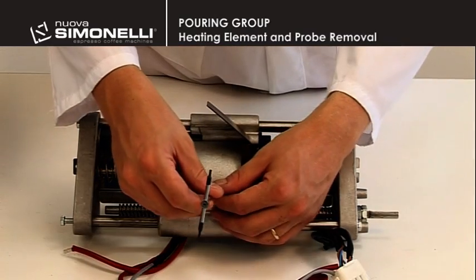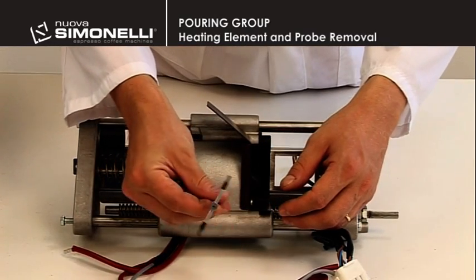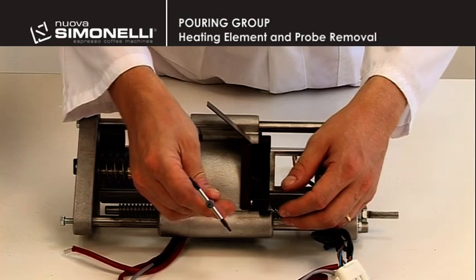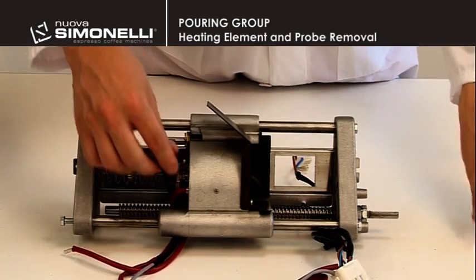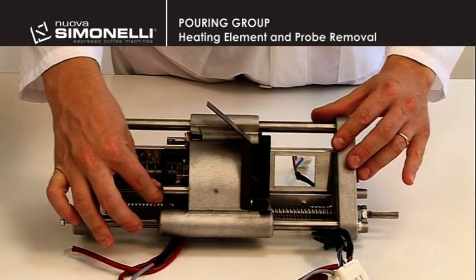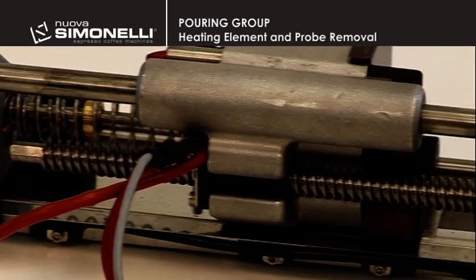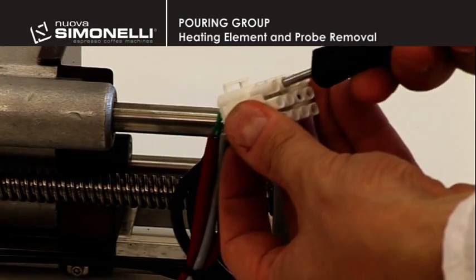Heating element and probe removal. To remove the heating element, loosen the 2mm Allen screw and slide it out. Free the wiring from the clamps and then use an extractor to disconnect the two pins from the wiring connector.